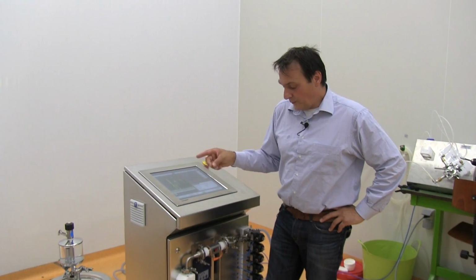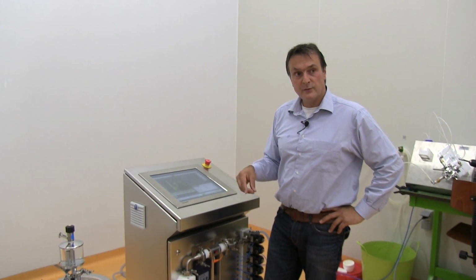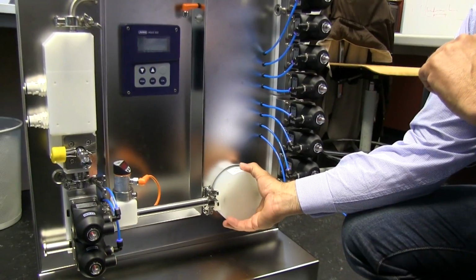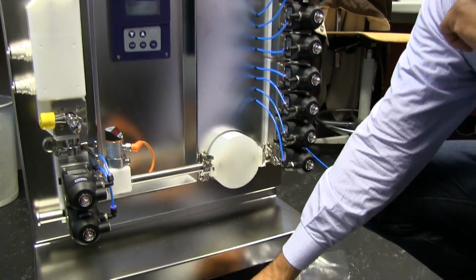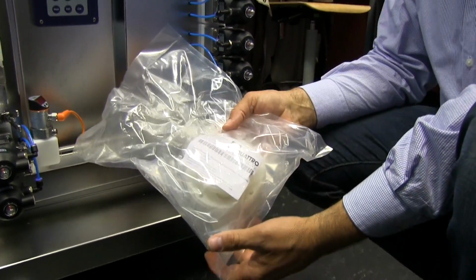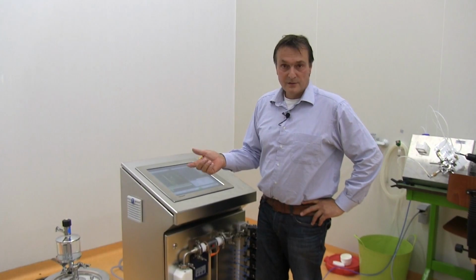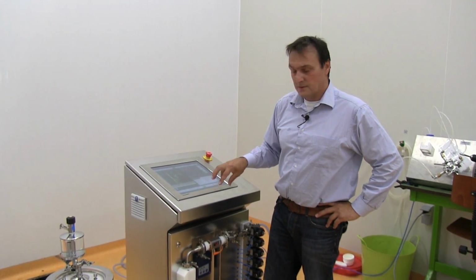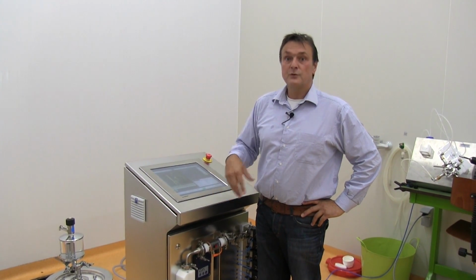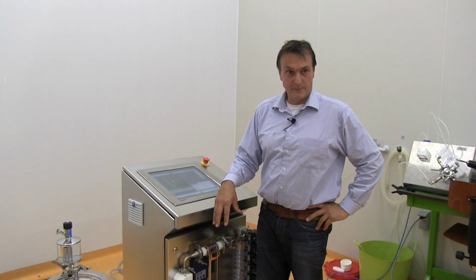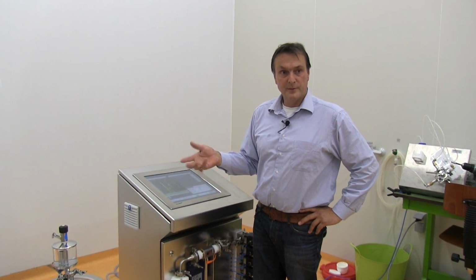In this setup, we are using disposable heads on the Quattroflow pump, and that disposable head is switched for another head which can be used in process. So if you're switching the system from packing mode to process mode, you take another pump head, clean out the tubing, and you are ready to go.